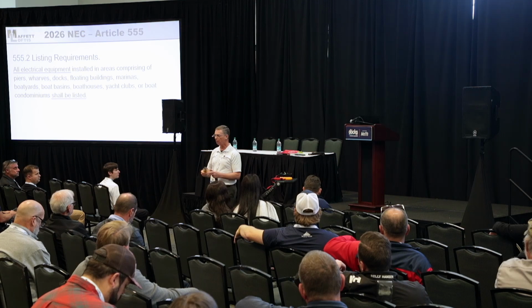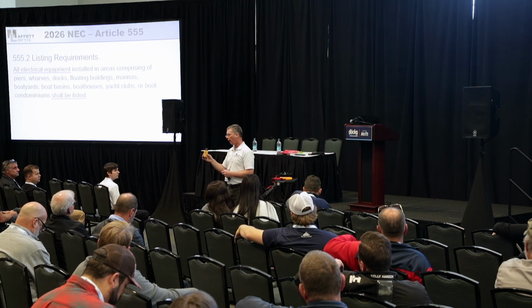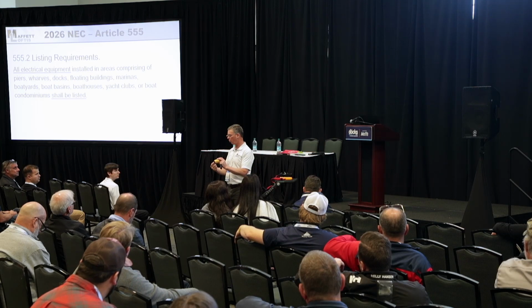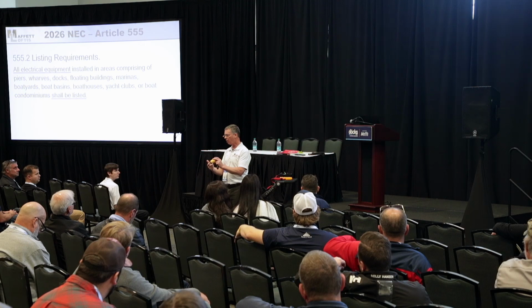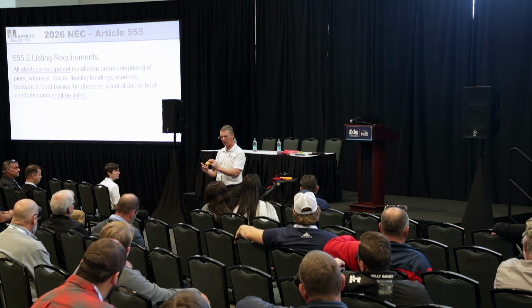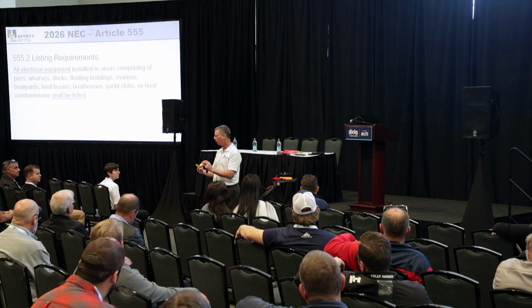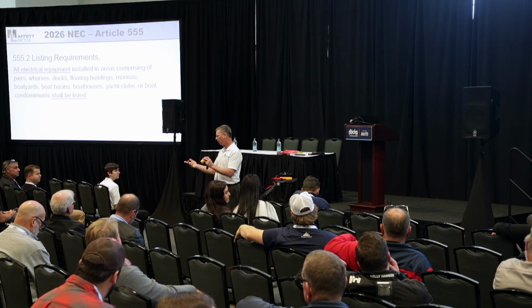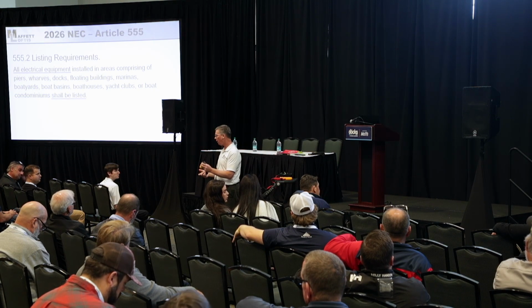So I would recommend not using these, and instead have a duplex receptacle that is GFCI, rather than plugging into a 30 amp overcurrent protection. Because what type of cord is plugged into that? It's not a 30 amp cord. It's maybe at best a 14 gauge, 15 amp cord that you buy from Home Depot. It may even be an indoor, 2-wire cord, without even having a grounding system on it.